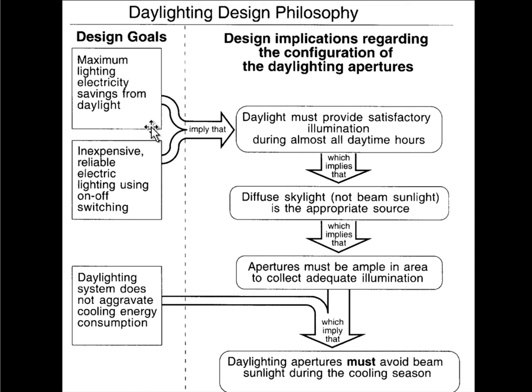We'd like an inexpensive reliable electric lighting system that uses on-off switching. Dimmers cost more money, they tend to be less stable, less durable, and they also pull a substantial amount of power even when the daylighting is more than adequate to illuminate the space. So if we can design a really good daylighting system that provides adequate light during almost all hours, the electric lighting system can be fairly simple and inexpensive, and once it's turned off we know it's turned off and we know we're saving 100% of that energy.